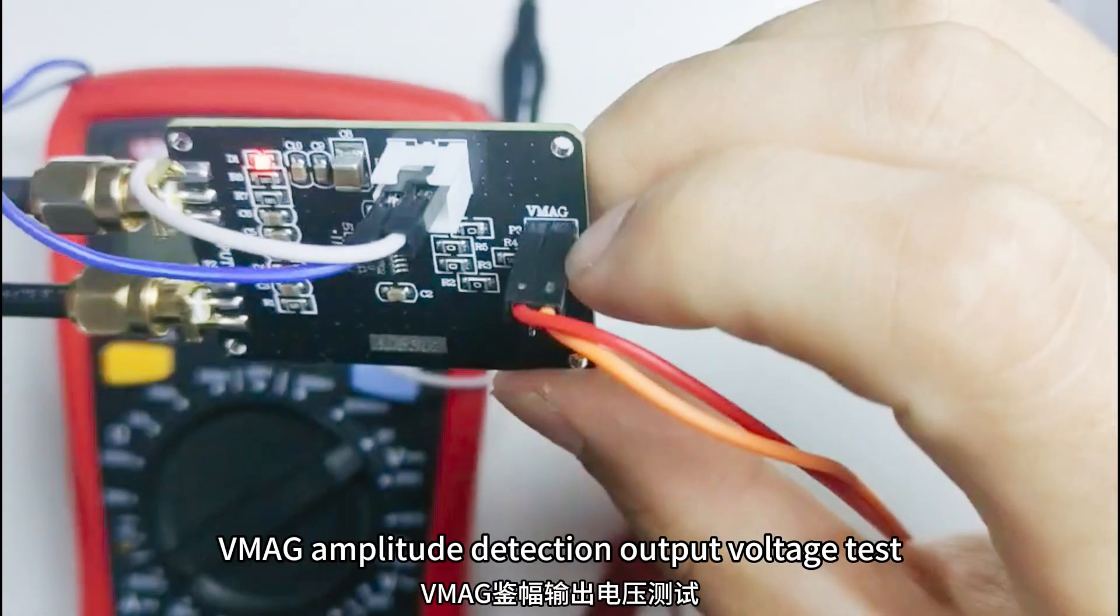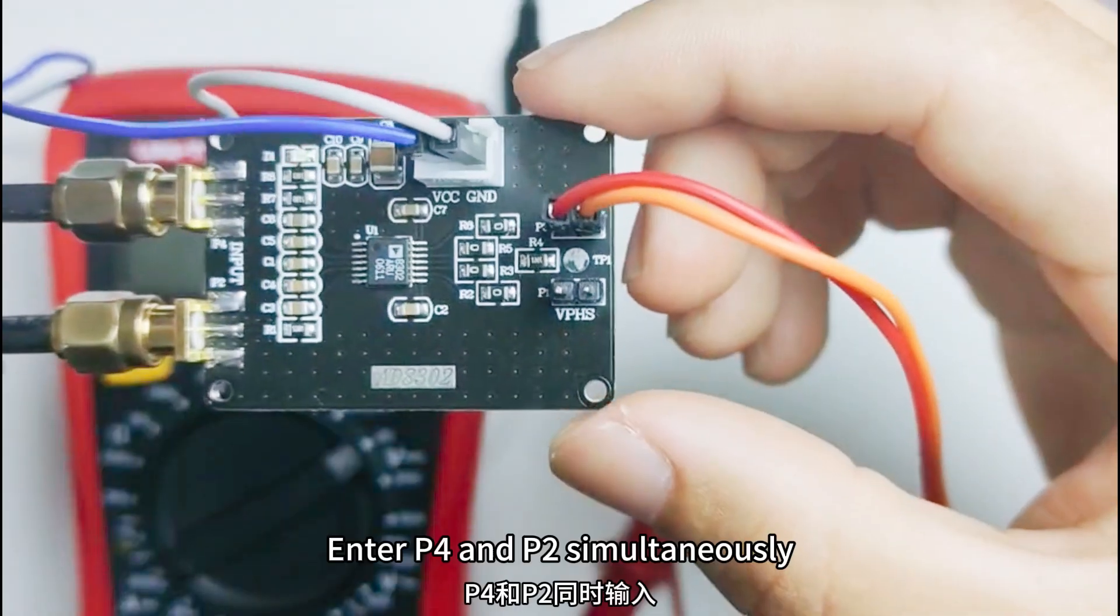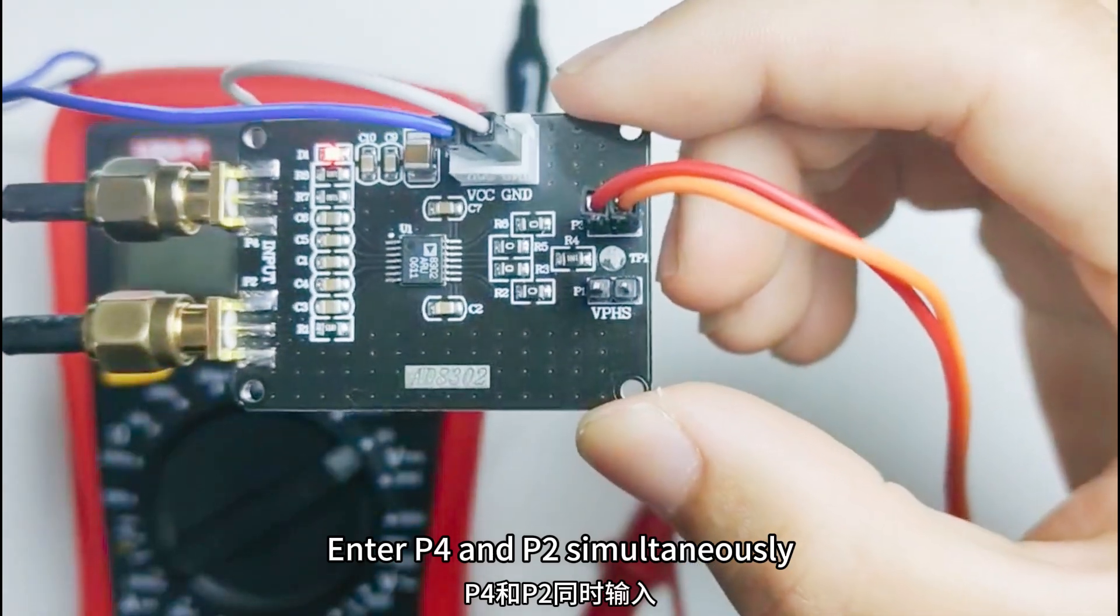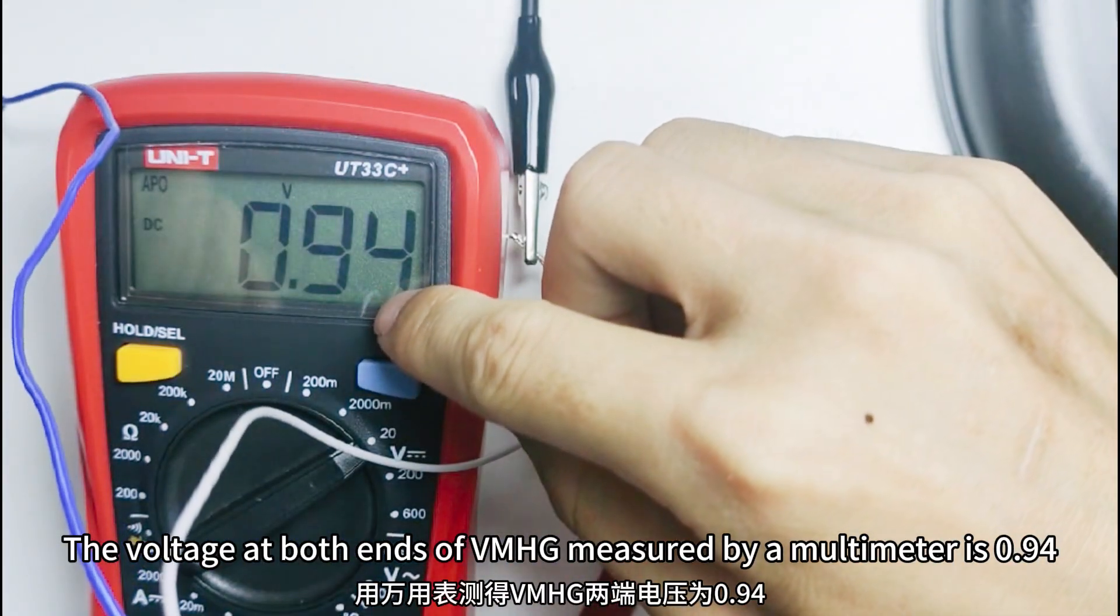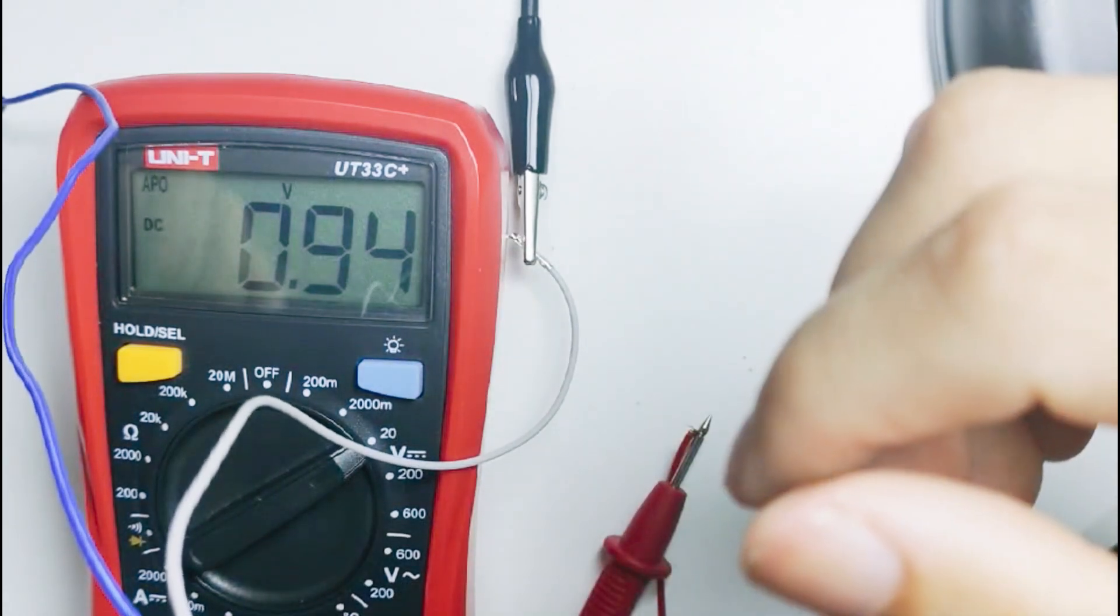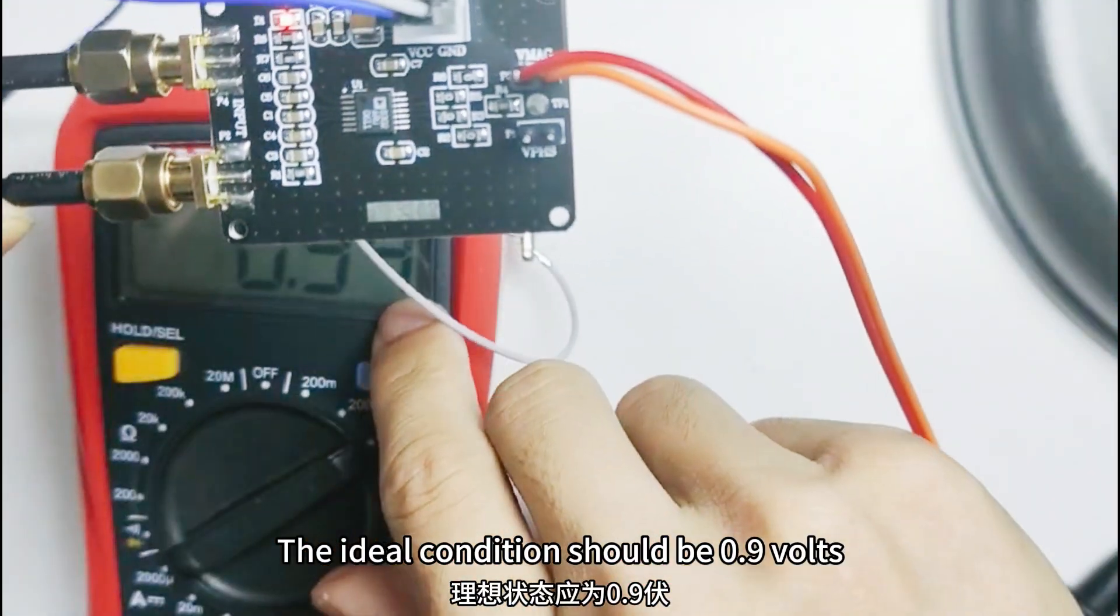VMAG Amplitude Detection Output Voltage Test. Enter P4 and P2 simultaneously a sine wave with an amplitude of 560 mV. The voltage at both ends of VMAG measured by a multimeter is 0.94. The ideal condition should be 0.9 V.